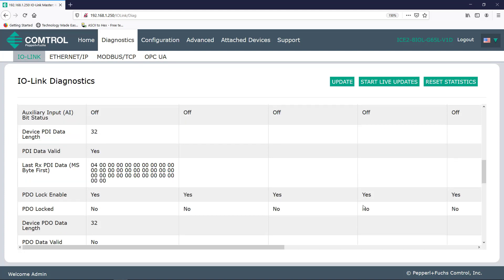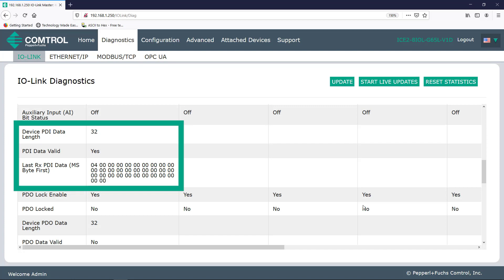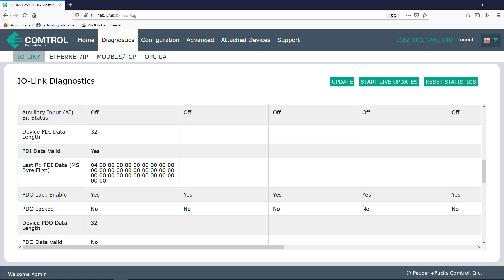These next three rows cover the process data input. So for instance, how many bytes does our connected read head allow? The device PDI data length says it right here, 32 bytes of data are available. And we see that the current status of the PDI data as received from the IO-Link device is valid. And below, I not only see that the IO-Link master regards this data as valid, but you can literally see all the data below.